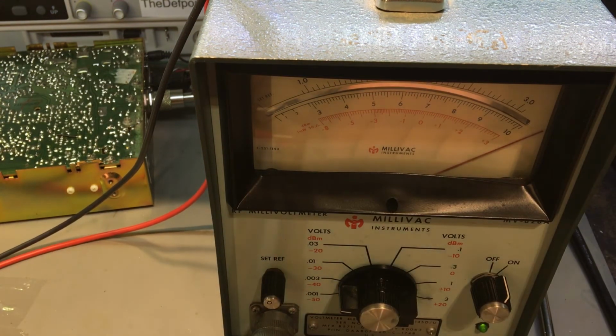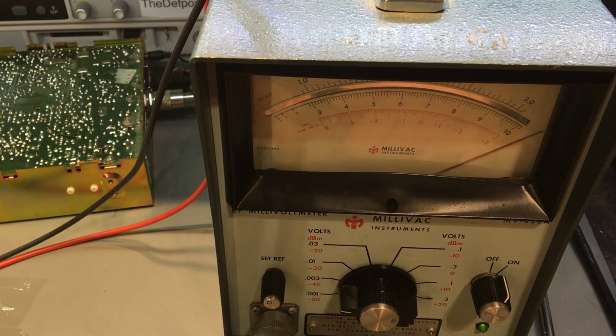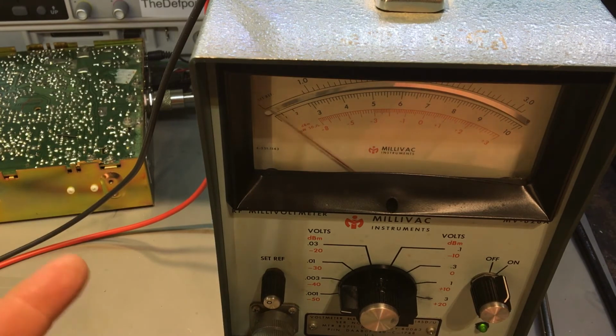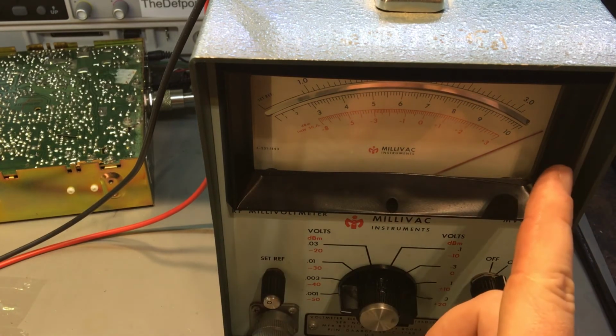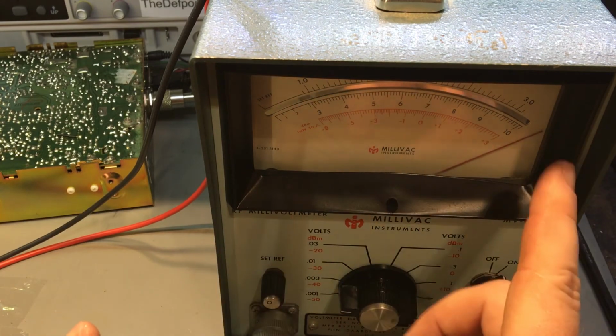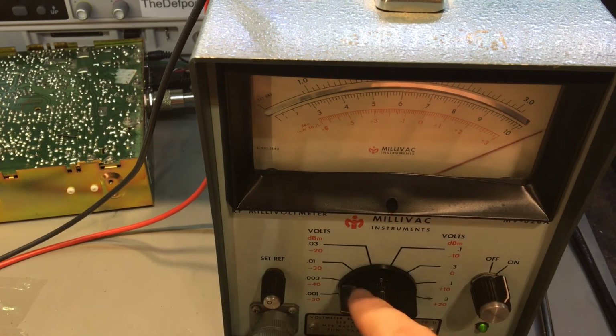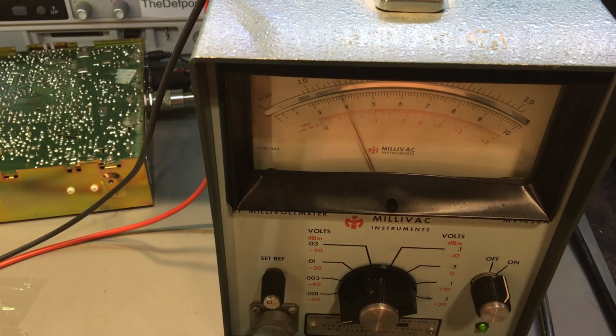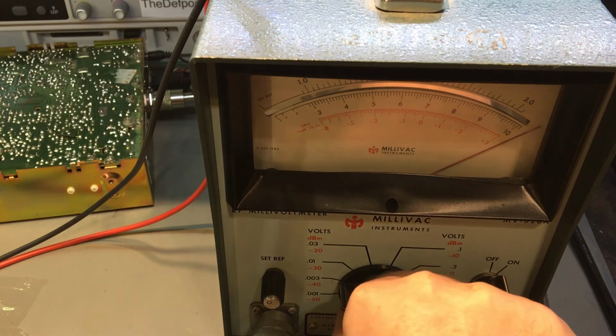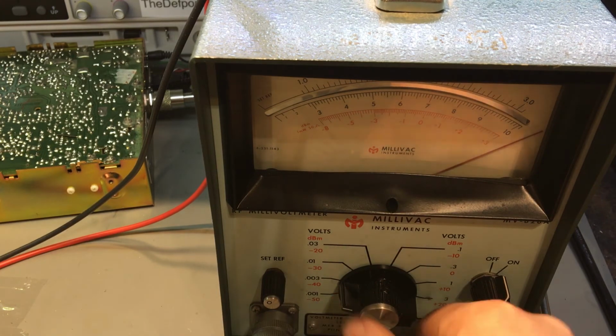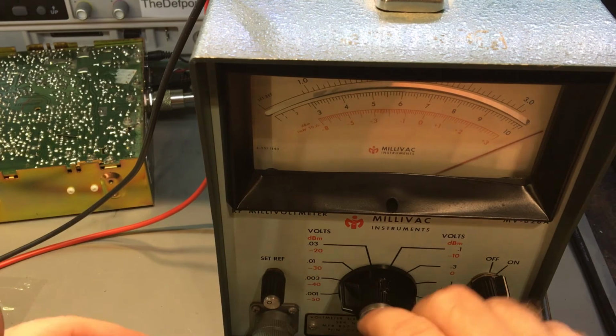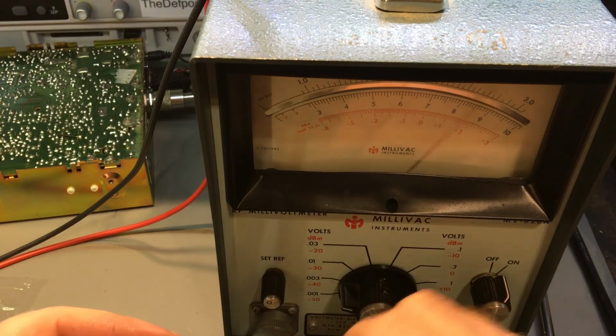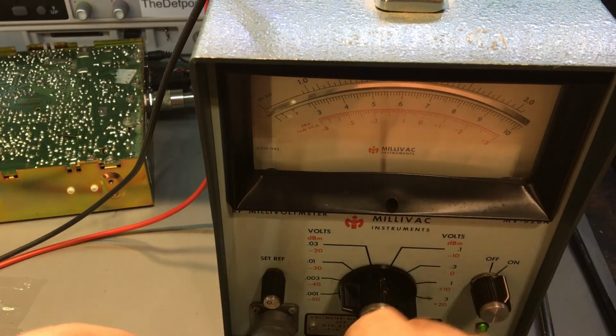If I actually disconnect the probes, there's now no probe connected, and it's still full scale. There we go, see it bounces, it goes down, comes back. It'll do that every once in a while. So there's an issue here on these ranges. On the bottom range as well, same deal. It does something different. So it looks like there might be a leaky capacitor there somewhere or something like that. Moving the probe around doesn't seem to change anything much. I don't know, it's just a bit erratic anyway.